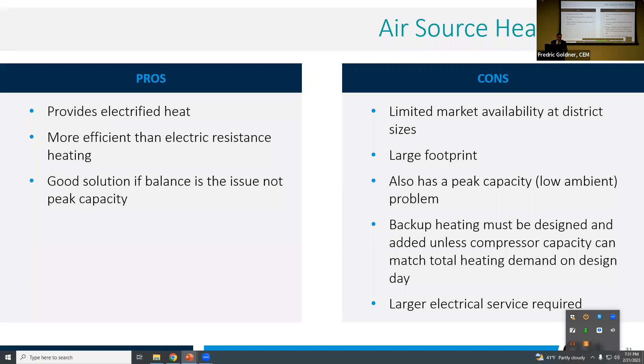Cons: limited market availability at district sizes, large footprint, and peak capacity issues at low ambient temperatures. What does that mean? When I need the heat the most, it's the coldest outside, and that air source heat pump isn't working as efficiently when it's cold. You typically have to bring up auxiliary or backup heating elements anyway, so now you've got two heating systems in effect, and of course a very large electrical service requirement.